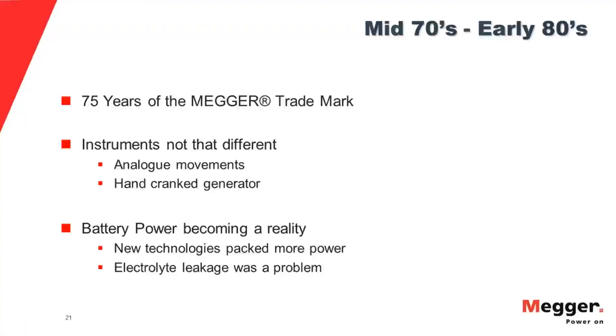Another thing that they would do is, as they started to get low, the accuracy of the readings would start to drift. So if you go back to maybe the 50s or 60s, early 70s, there were a number of papers that were written pretty much denouncing battery power. And some of those you might still see around, and if you ever run into an application note like that, take a look at the date on it. Because beginning around the 80s and into the 90s, there was a rapid advancement in battery technology that eliminated all those old problems. But experienced operators still remember them, I'm sure.